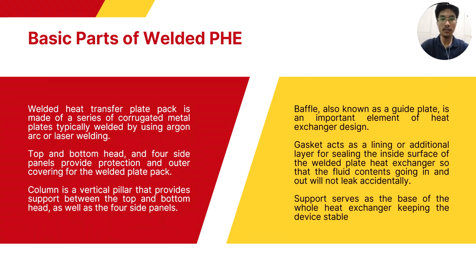So it is one of the most important parts of a welded PHE. The plates that are used on this welded heat transfer plate pack are basically made of strong metals and highly resistant to corrosion or rusting. So these are stainless steel, carbon steel, nickel alloy, Hastelloy, and titanium, and many more.